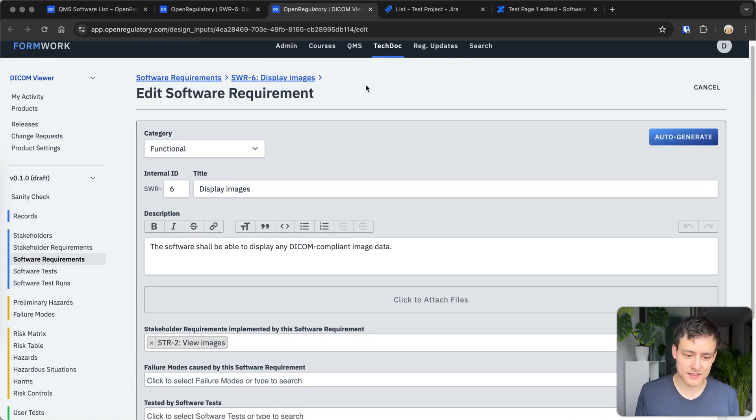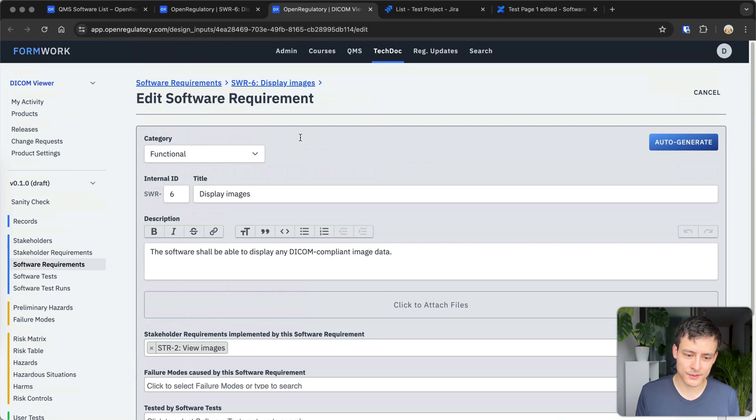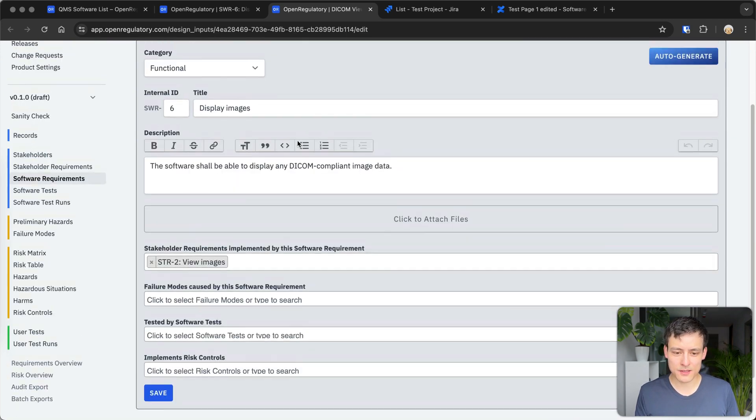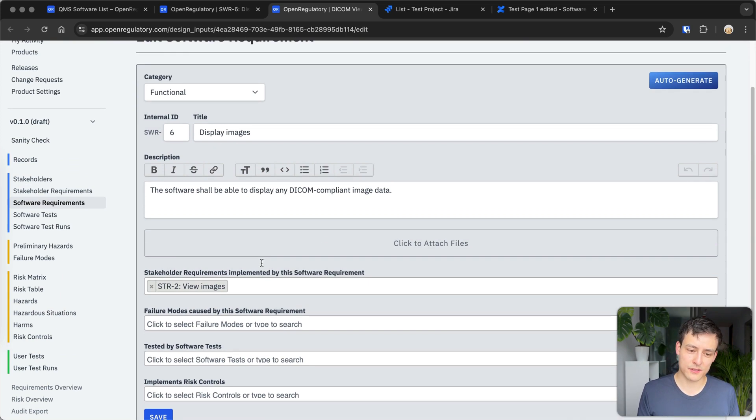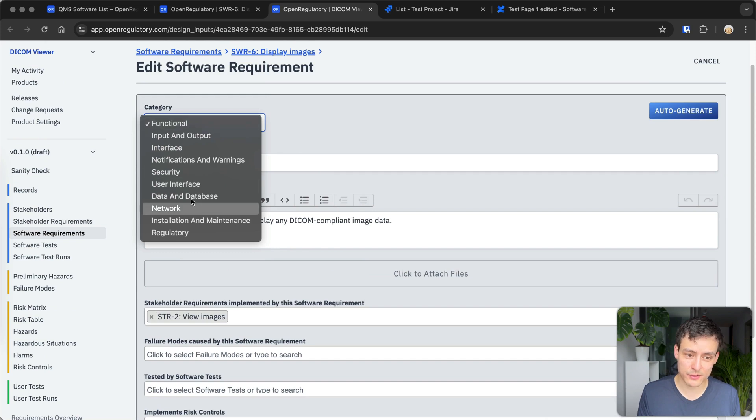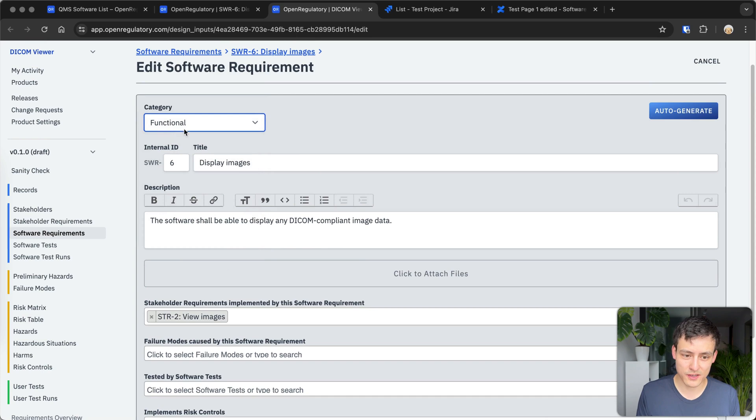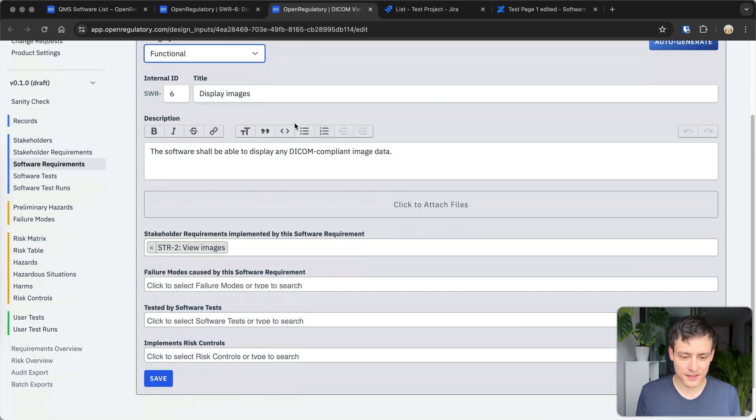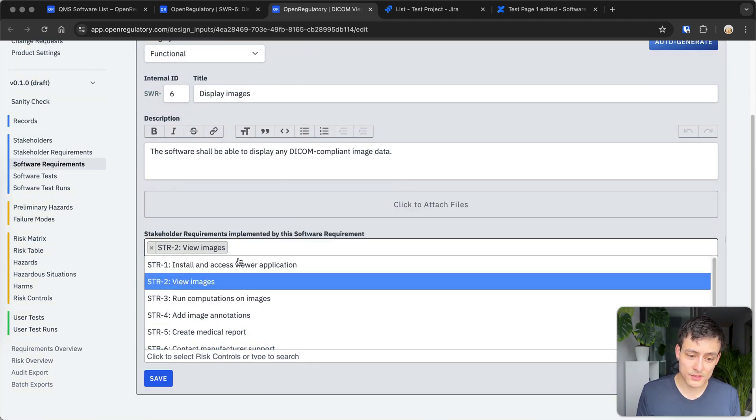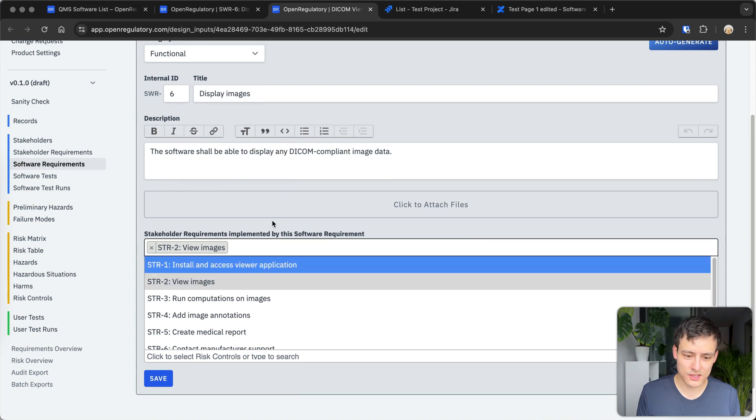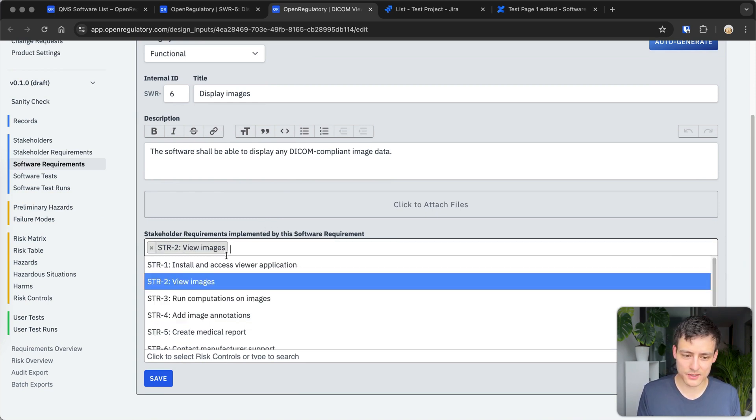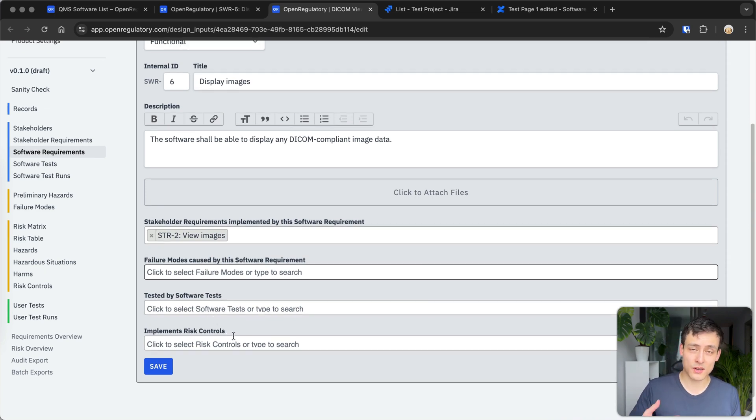So if you edit it, this is how it looks. And I think this makes it even more clear. So in our software, and again, this is not necessarily about our software, but it's just about predefining these form fields. So we predefined these form fields for you. So you have a category and these are actually the categories from the standard. So you have to associate one category with it for the software requirement. Maybe it's a functional requirement in this case. Then you can select a user need or stakeholder requirement to associate it with, like you essentially have this many-to-many relation going on here. Same for failure modes, same for software tests, same for risk control. So all of these are regulatory requirements.